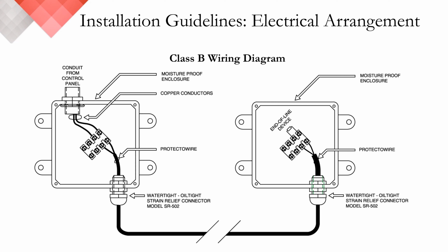The detector is then run through the zone as needed and prescribed, and then landed at the end of the zone in your end-of-line box. From there, we're making the same connection points as we did in the beginning. The only difference is here we're conditioning the line with the end-of-line resistor. Where linear heat is classified as a non-restorable fixed temperature device, the only testing required is to short the detector at the end-of-line resistor. Inducing an alarm or a fault condition from this point confirms the detector is intact and communicating properly with the panel.